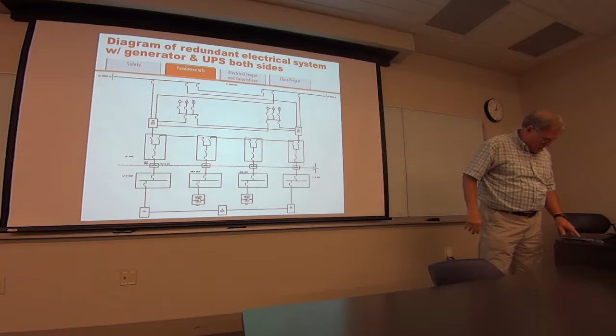Yeah, they'll handle both of those events. Double conversion UPS takes AC, converts it to DC, charges the battery, and then takes the DC and reconstructs the AC. So whatever this does over here, it's kind of got a big sink where it dumps charge, and they've got ranges of voltages that they'll tolerate before it goes into the battery. So generally that would be a good plan for us because that provides a lot of stability. Yeah, you really do need that, in part of it you need that.